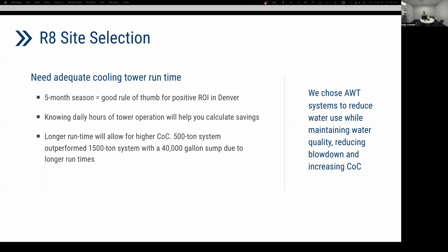And then one other note is about longer run times. We compared a 500-ton cooling tower system to a 1,500-ton system, and within that, the 500-ton system still had more savings due to the higher cycles of concentration it was able to achieve, coupled with longer run times overall. So it really depends on your site parameters as far as what savings are available and how much you'll achieve.